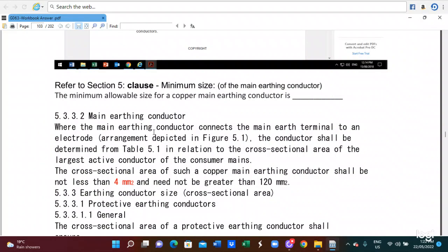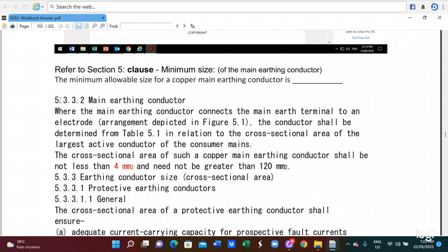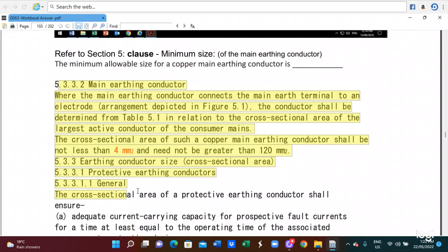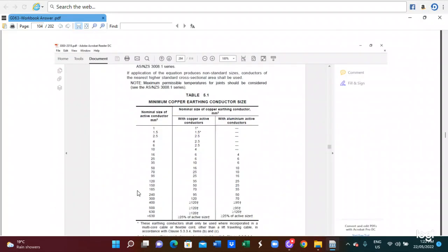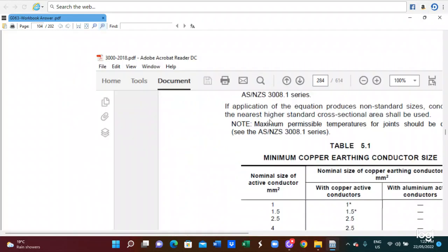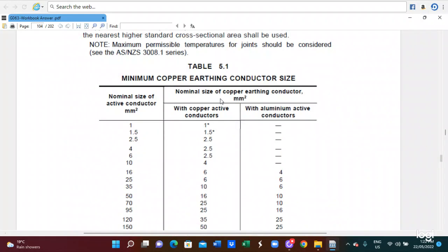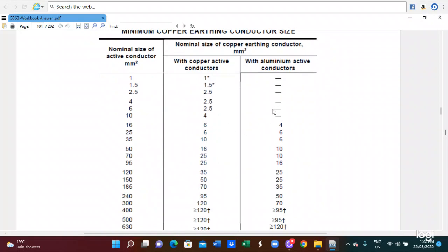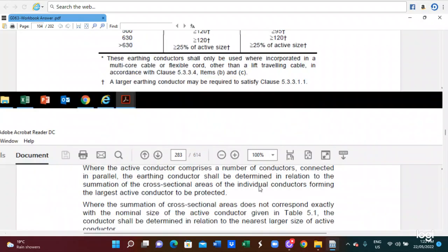So for the main earthing conductor, you refer to clause 5.3.3.2. This is the main earthing conductor definition. How to install the main earthing conductor, you have to refer to this clause. And also Table 5.1 gives the minimum earthing conductor size. You can read the minimum earthing conductor size in Table 5.1 depending on the active wire size, so this is the minimum earthing conductor size you can select from this table.